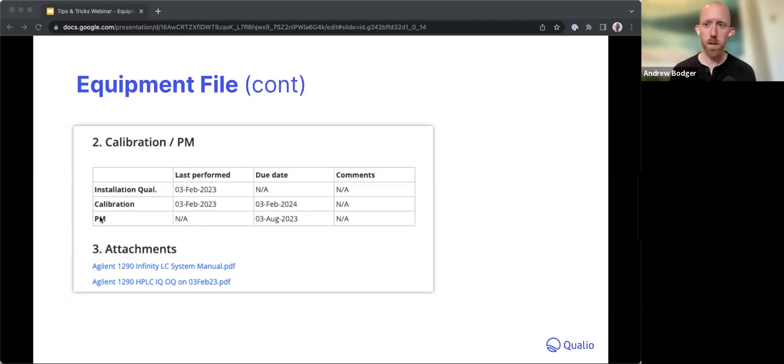So in this case, hopefully my math is right, it's just going to be August 2023. That's your next service. So you would set your periodic review to be 3 months from now. And then when that service completes, you would update your periodic review to say 6 months, because that's now when the next service date is coming up. So yeah, you won't be able to differentiate that in the document, and of course you wouldn't really be able to get that differentiation in the analytics feature.